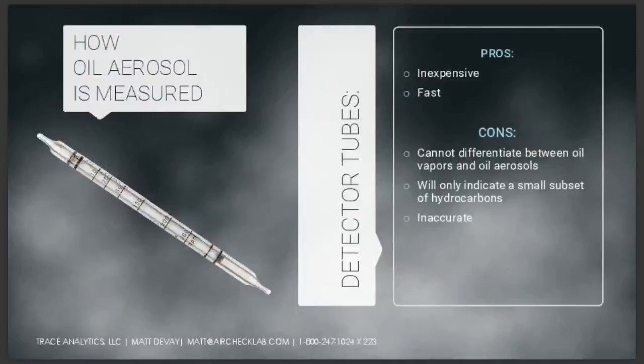A lot of people really like to use detector tubes to measure oil content, and we'll come back to these when we see oil vapor as well. It's essentially the same tube that measures both, but there's a lot of caveats. They are advantageous in that they're inexpensive and fast, but some of the problems, they don't see everything that might be oil. Typically, these have a few target compounds that they're calibrated against, and so, what if you're using a silicone oil? A lot of these don't respond very well to silicone oil. Sometimes these things respond really well to things that are only minor components of your oil vapors or oil aerosols. It can't differentiate between oil vapor and oil aerosol. So that can be a problem depending on what you need.